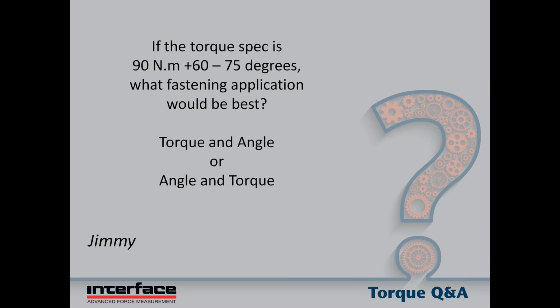But we don't necessarily have anything specific that really does the testing, so I can't really address that part of it. Keith, you're exactly right. There are a variety of suppliers that supply automated fastening equipment, and if you're applying a torque to a cylinder head bolt, for example, the specification is defined as a torque plus a certain degree of rotation, and it is an automated feature. We would potentially offer equipment that could be used to check or validate the accuracy of that type of equipment, but we don't have the functionality of being able to do positive torque and angle or angle and torque control.